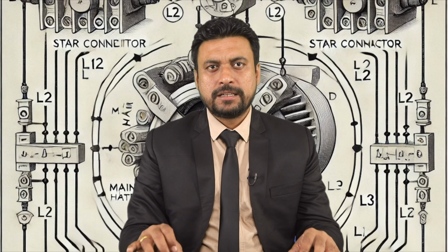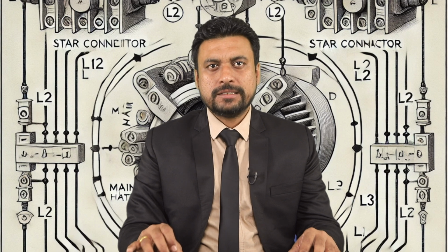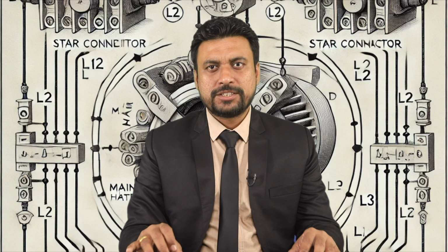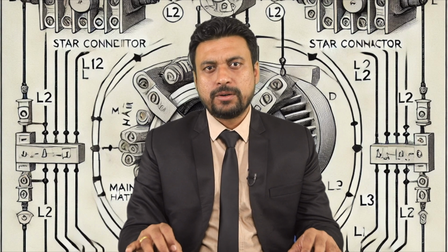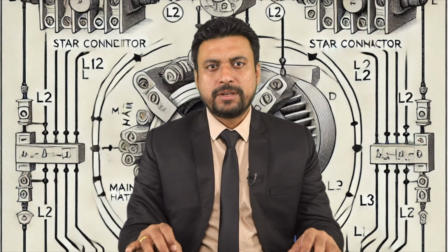Now let's see the operation of a star delta starter. This starter works by initially connecting the motor windings in a star configuration, which reduces the voltage across each winding to 1 by root 3, that is approximately 58% of the full line voltage. This reduction in voltage leads to a significant decrease in the starting current, typically to about 1/3 of what it would be if the motor were started directly in the delta configuration.